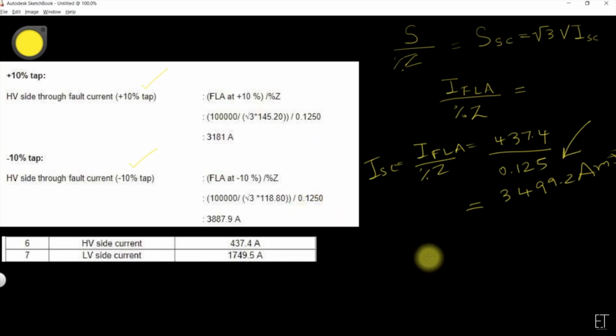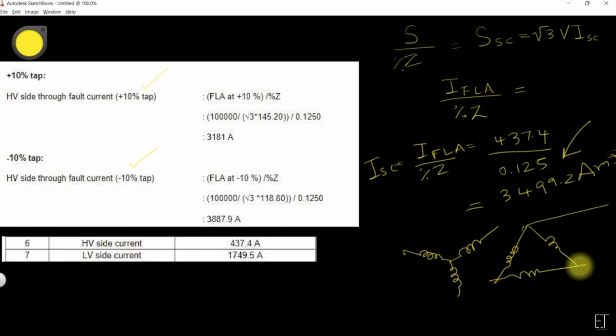So what is a through fault current? If you consider a three-phase transformer, for example a star delta transformer, and there is a fault on the line or the terminal of the transformer, then current will flow at the LV side and HV side. This is called the short circuit current, and this current is called the through fault current or short circuit current of the transformer. We have shown how to calculate the current for the high voltage side. In the same way you can calculate it for the low voltage side.